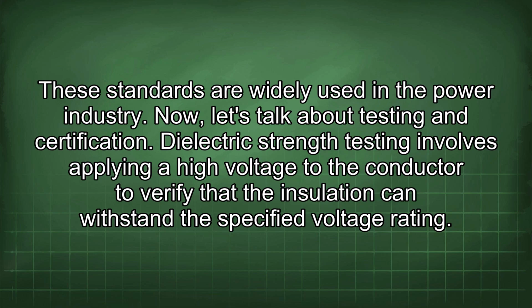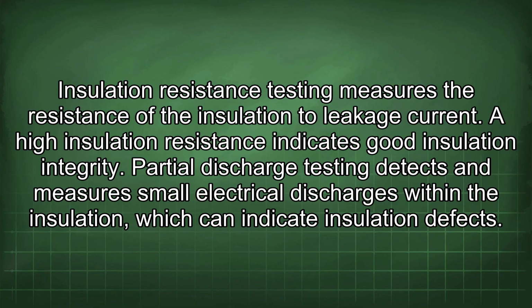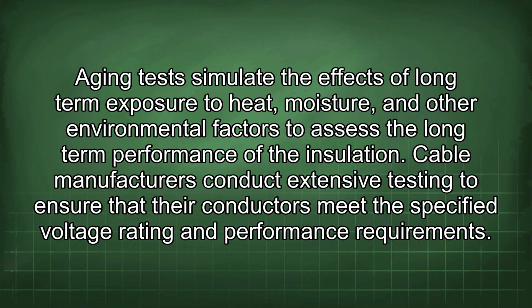Dielectric strength testing involves applying a high voltage to the conductor to verify that the insulation can withstand the specified voltage rating. Insulation resistance testing measures the resistance of the insulation to leakage current. A high insulation resistance indicates good insulation integrity. Partial discharge testing detects and measures small electrical discharges within the insulation, which can indicate insulation defects.